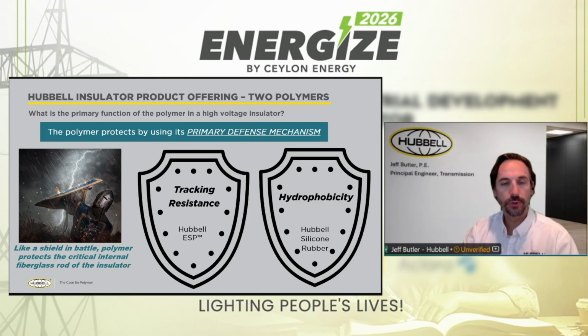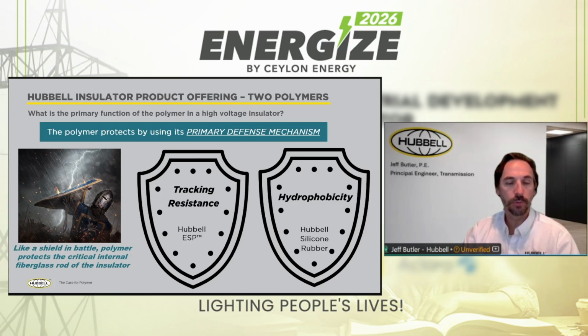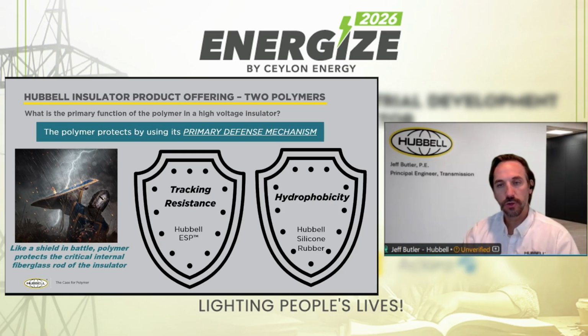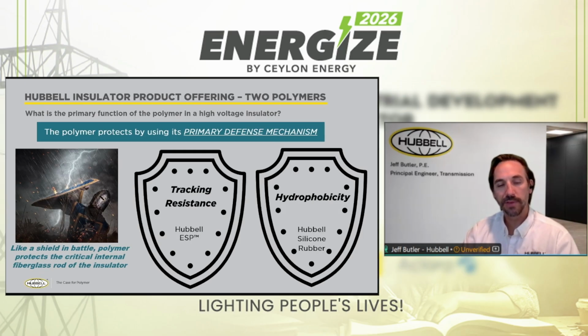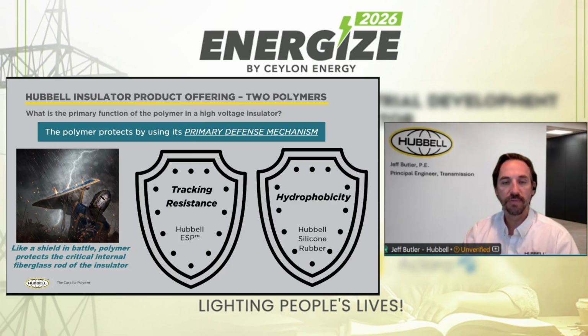So for Hubbell, we use two different types of polymers. So I have two shields represented there. The one in the middle of the screen I'm referring to as the Hubbell ESP. ESP is an acronym that Hubbell uses to define our distribution or our ethyl-based rubber. It stands for Enhanced Silicone Polymer, and it's an EPDM, or an ethylene propylene diene monomer, blended with a silicone rubber that creates a polymer alloy. And the primary defense mechanism for that material is tracking resistance. It is very tough. It is a durable material. So even if electrical activity is occurring on the surface of the rubber, it's going to be able to withstand that electrical activity for a long time, for a long duration.